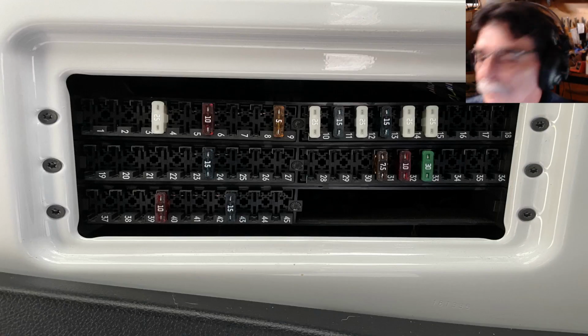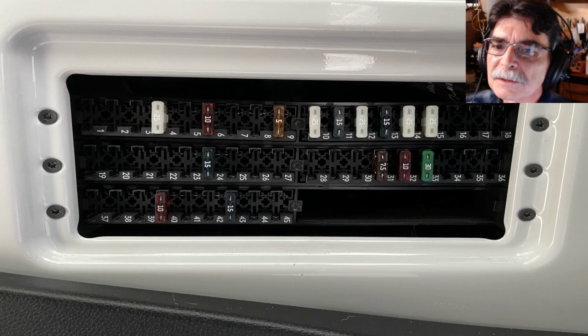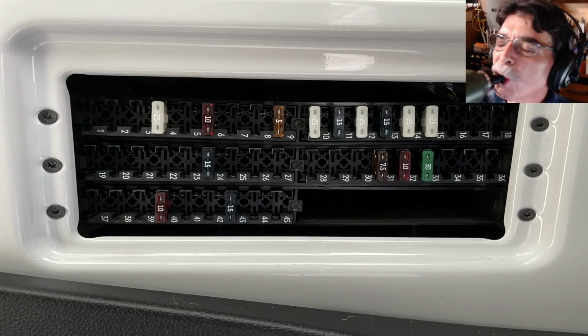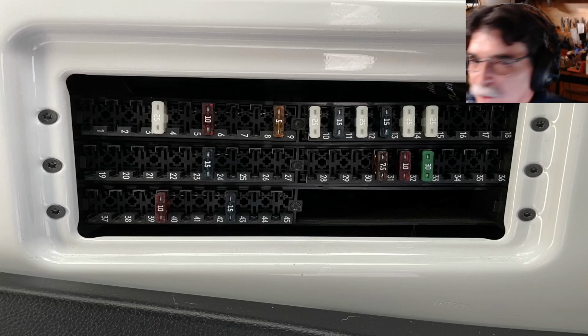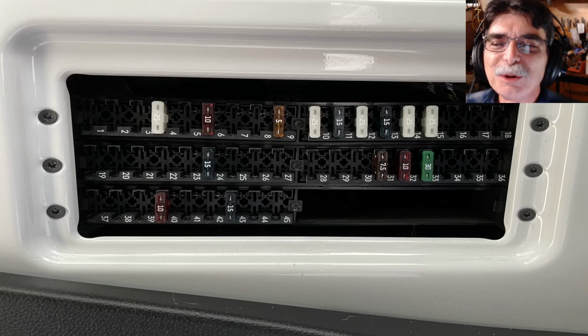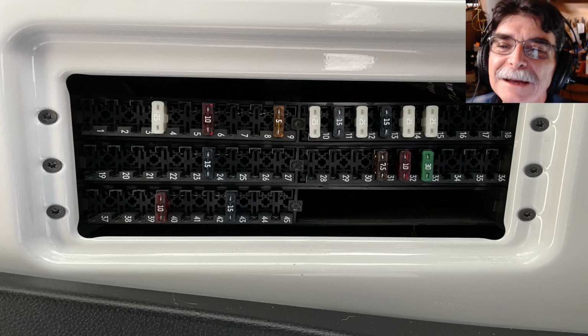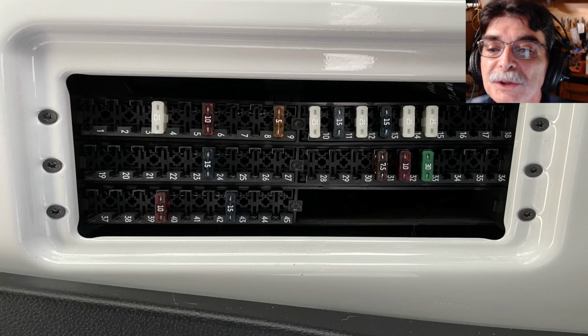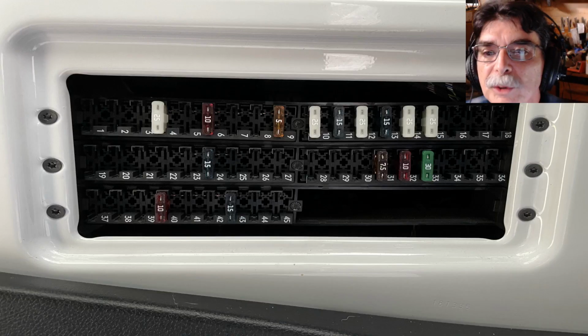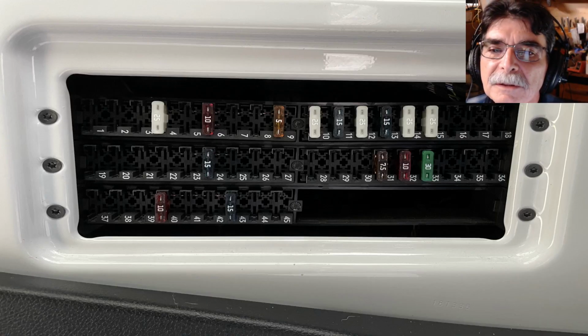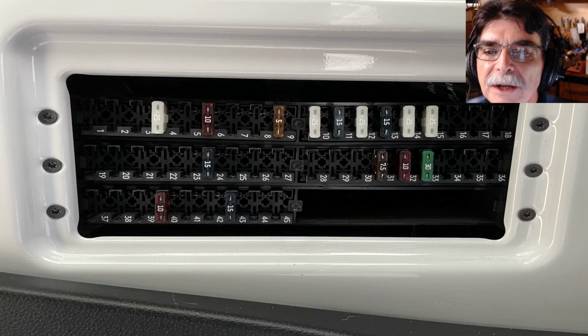Here's a quick tip. You see there's a lot of empty slots in there. Do not indiscriminately just pull fuses out, because they're going to be hard to remember where they go back in. My suggestion, if you do need to remove one, is to take a picture with your phone, straight on. Don't be standing up looking down at it, because you get what we call parallax, and the picture won't give you a true indication of where the actual fuse is.